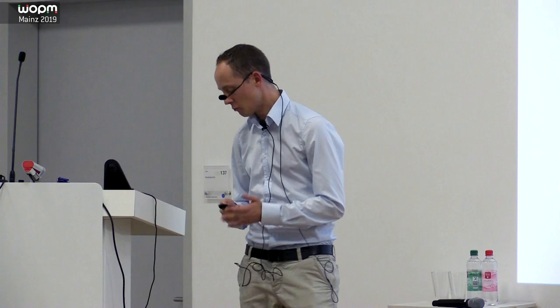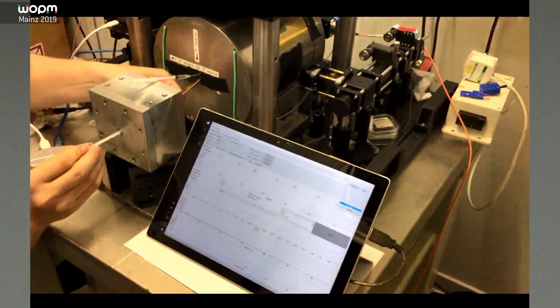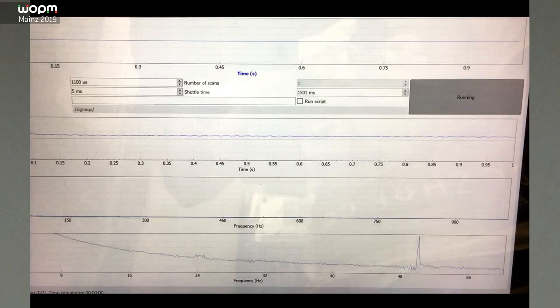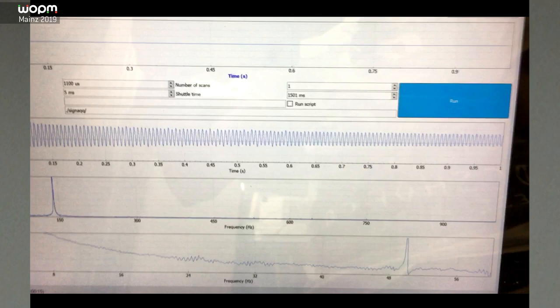In reality, well that is much more complicated when compared to this simple animation. So what we're seeing here, we're just pressing a button, then we use the syringe to move the polarized nuclear spins into the ZULF spectrometer, and then we apply the pulse, and just a few seconds later we see a very beautiful free induction decay signal that can be used for further analysis.